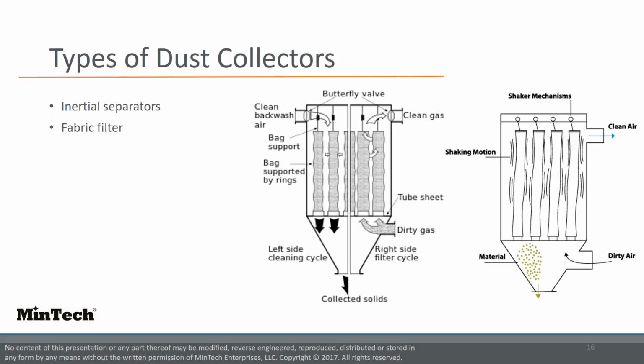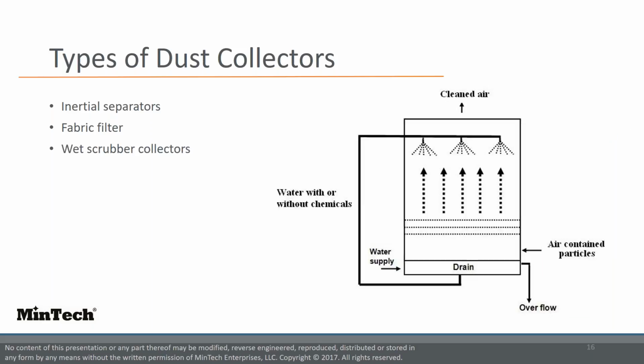Second, you have fabric filter collectors. These employ bags, cages, and venturi assemblies to remove dust from the airstream through mechanical filtration. The efficacy of these units is largely dependent on the filter medium, which can be modified to only capture large dust particles or modified to capture extremely small dust particles, such as the case with HEPA filtration.